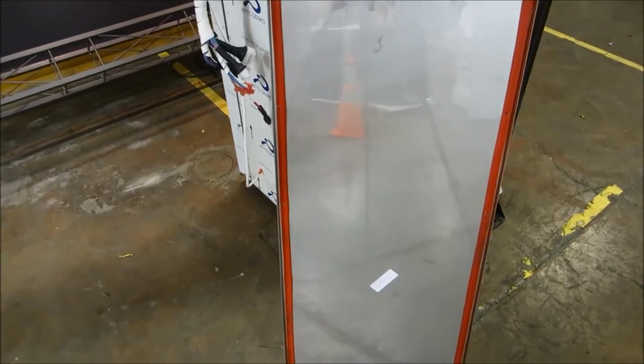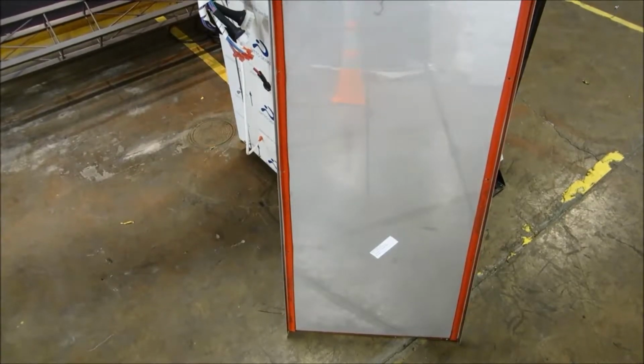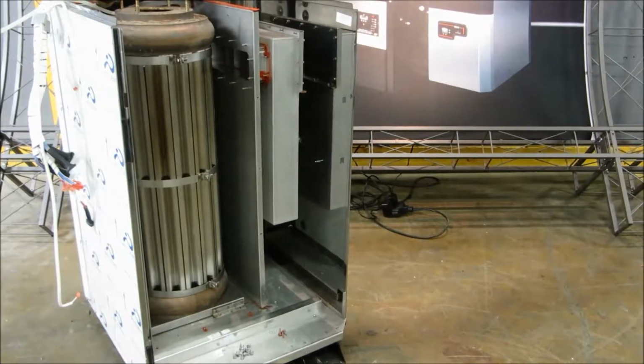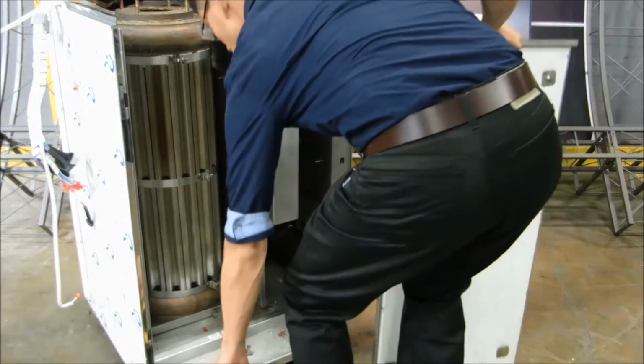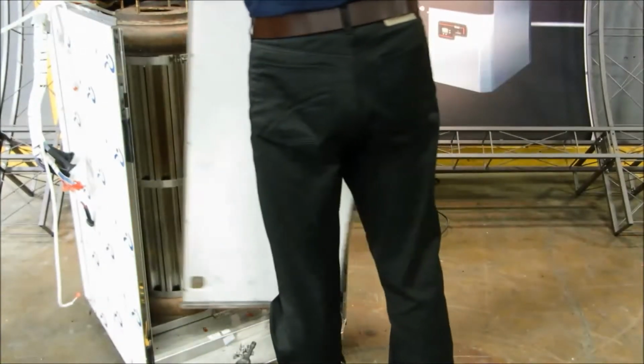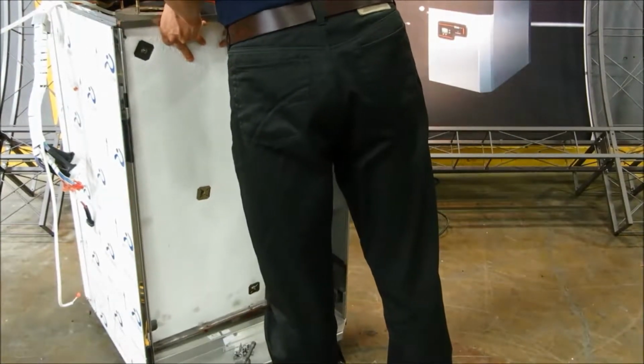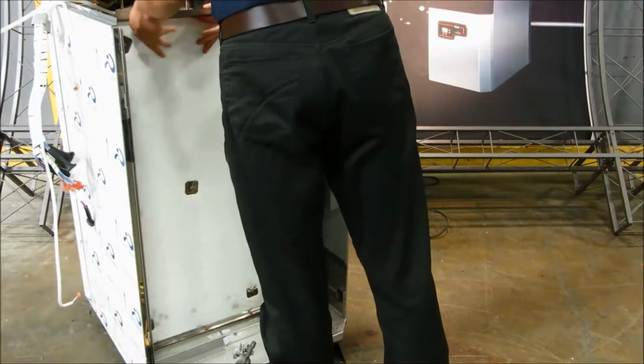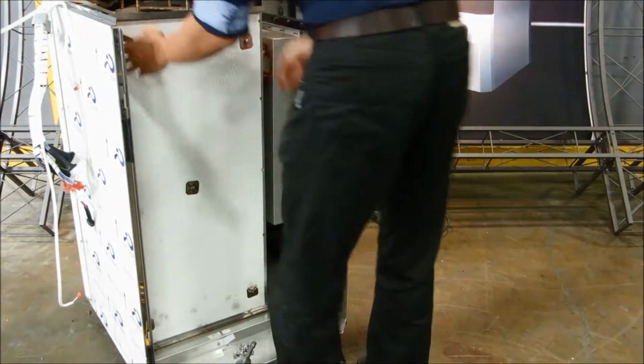When installing the front combustion chamber door and top panel, check the red silicone strip gaskets. If the red silicone strip gaskets are torn, they will need to be replaced. Do not replace just the torn section, you will need to remove the entire gasket. Be sure to scrape off any remains and re-gasket it, as patching the damaged section will allow combustion gases to escape.